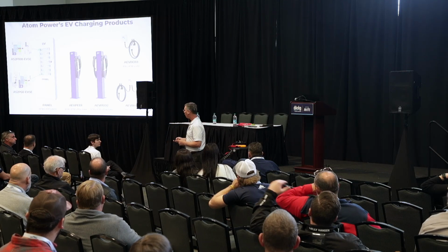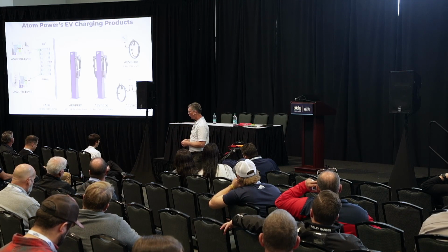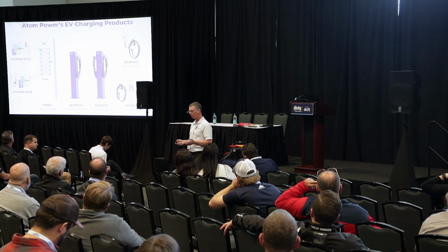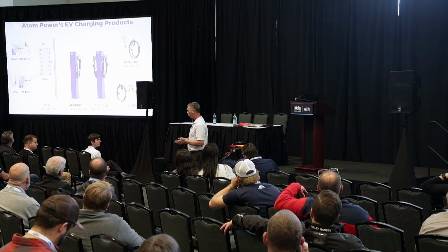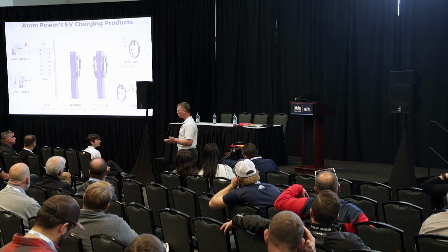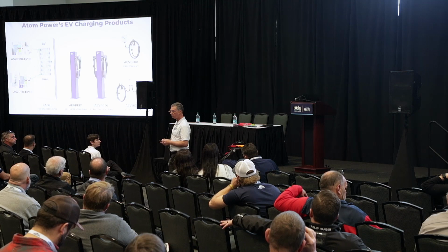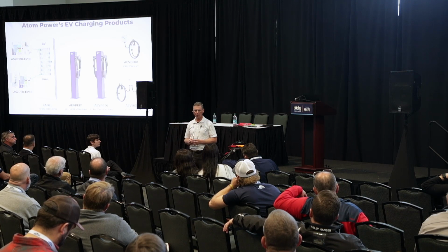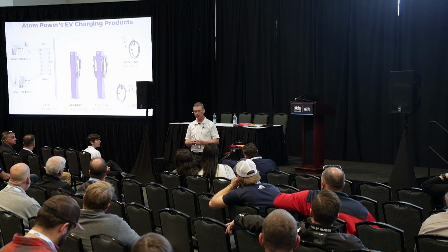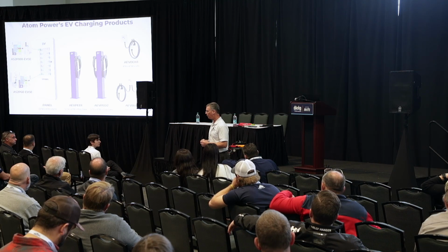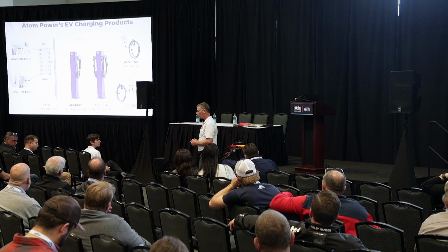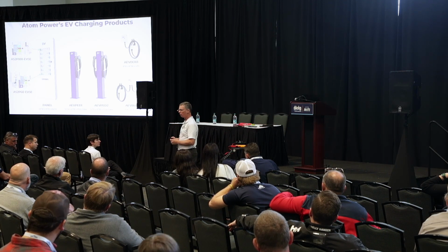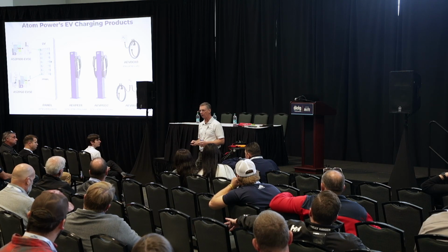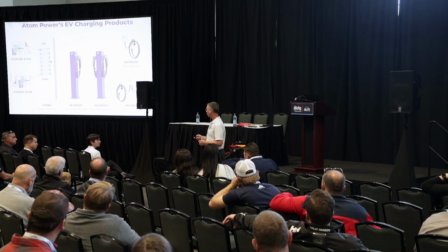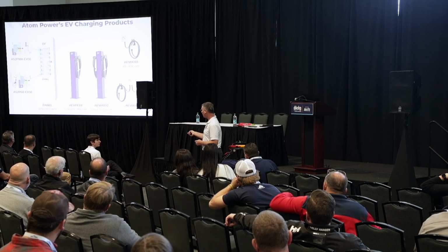So that's what we're talking about as far as doing the load study — you can have a lot more connected load, even though the NEC would normally require 1,200 amps worth of switchgear, but now you only need 400 amps worth of switchgear. That can be a big cost savings, and even a revenue process if you want to look at doing electric charging for boats. I've actually designed some systems with this.